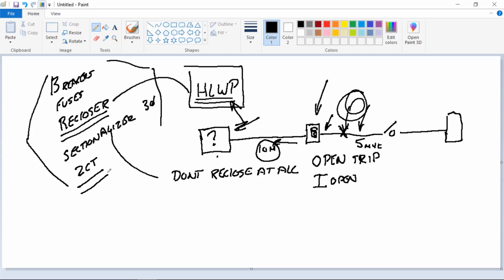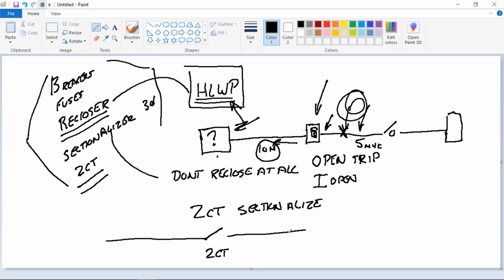Now, here we go. 2-count sectionalizer. Here's my feeder circuit. I'm just going to put a switch here to designate it. Here's my 2-count. I'm working down in this area right here. Do I need to get a hotline work permit on this feeder circuit if I'm working beyond a 2-count? Yes. Why is that? Because it's going to register the fault twice. You're going to get an instantaneous open, and then what? It's going to reclose. How many times? Twice. That's why you need to get a hotline work permit on that circuit, because you're going to get an instantaneous reclose, and it's actually going to happen 2 times before the 2-count eventually does what? And blows open.